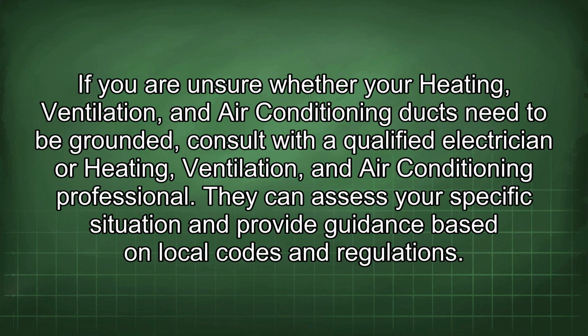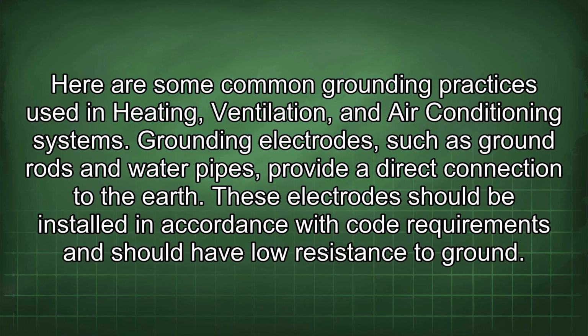If you are unsure whether your heating, ventilation, and air conditioning ducts need to be grounded, consult with a qualified electrician or heating, ventilation, and air conditioning professional. They can assess your specific situation and provide guidance based on local codes and regulations. Here are some common grounding practices used in heating, ventilation, and air conditioning systems. Grounding electrodes, such as ground rods and water pipes, provide a direct connection to the earth.